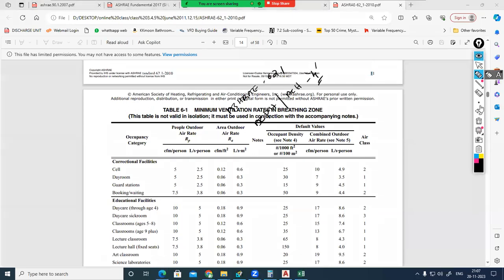And from this you can see minimum ventilation flow rate in breathing zone. And here you can see the occupancy category, what type of space you are designing. People outdoor air rate and area outdoor air rate. People outdoor air rate is called RP. This value we should take. Each person, how much quantity of fresh air has to be introduced with respect to the activity level. Both units, imperial system CFM and liter per second, are available. We are dealing with SI units, so we can go for the liter per second value.